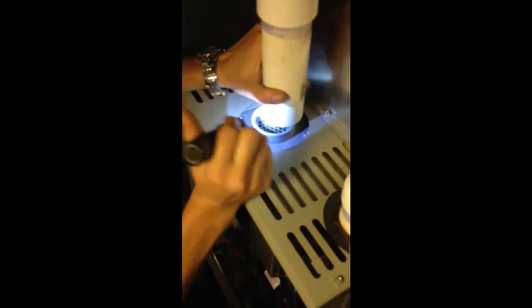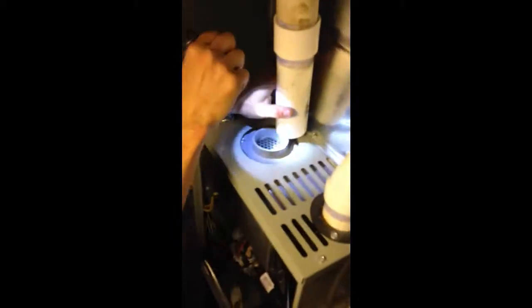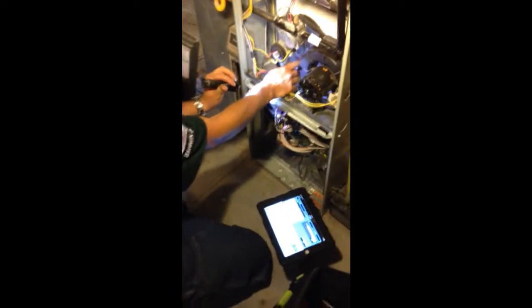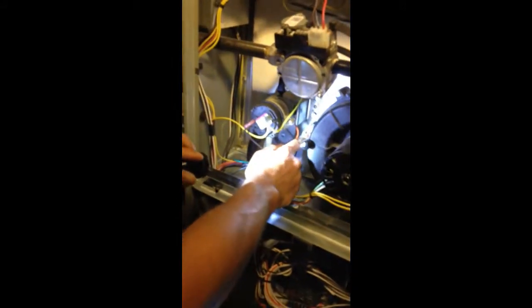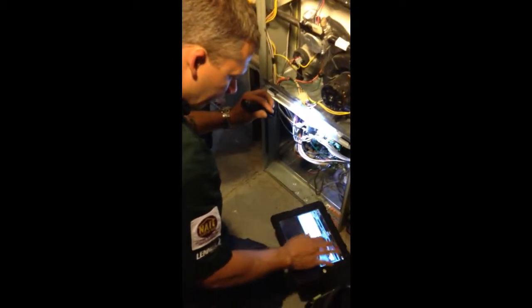Gotcha. We check the intake venting. Make sure there's no leaves, bunch of dead spiders. If that blocks that, then the furnace will stop running. So we pull this up, look in there. Make sure that's good. It's got a kind of weird bending. Here, it's grounded right there. You can see the green wires. These are grounding wires. They're grounded right to that. So we can say yes, the electrical's grounded. And we check the circuit board for burn spots, any sort of shorts or anything like that. I don't see any sign of that. Great.